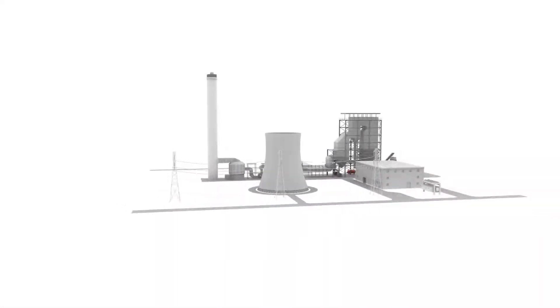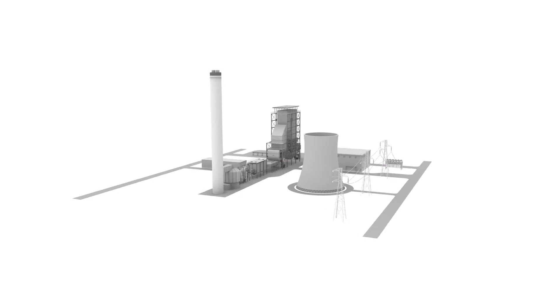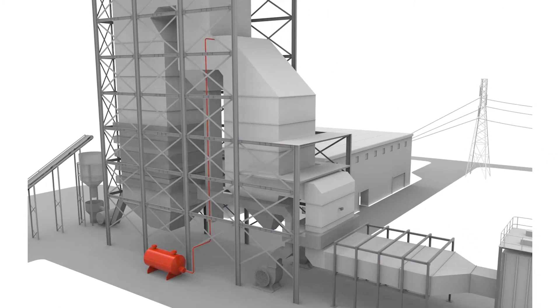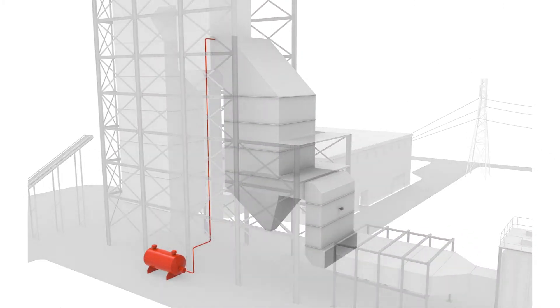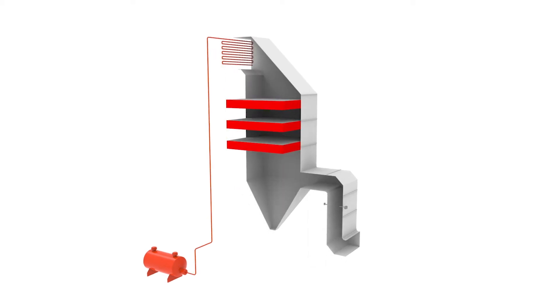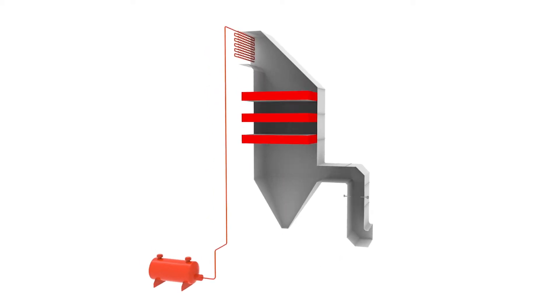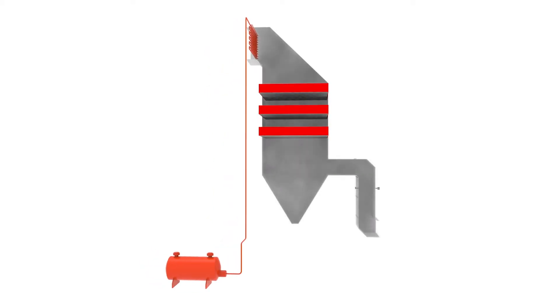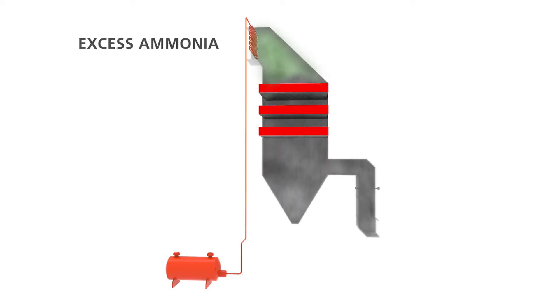Combustion processes produce harmful NOx emissions. Controlling these emissions requires the addition of ammonia to the flue gas in order to significantly lower NOx. To ensure as much of the NOx is removed as possible, an excess of ammonia is used. This is called ammonia slip.